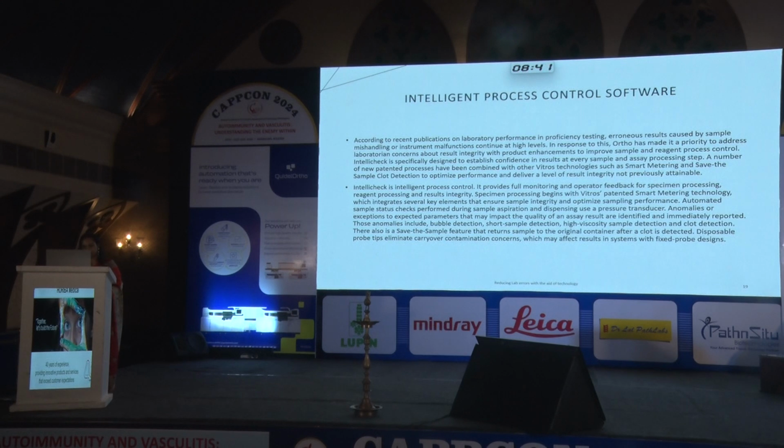IntelliCheck Intelligent Process Control provides full monitoring and operator feedback for specimen processing, reagent processing, and result integrity. Specimen processing begins with Vitros patented smart metering technology, which integrates several key elements that ensure sample integrity and optimize sampling performances. Automated sample status check performed during sample aspirations and dispensing use a pressure transducer. Anomalies or exceptions to expected parameters that may impact the quality of an assay result are identified and immediately reported.